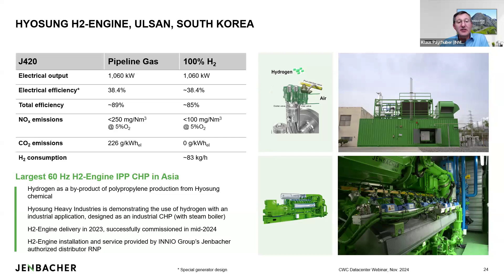What you can also see on this chart is the NOx emissions -- they significantly go down between natural gas operation and hydrogen operation. When running on 100% hydrogen, this engine produces less than 50% of the NOx emissions. The hydrogen comes from a polypropylene production as a byproduct, and the engine is installed and designed as a CHP unit. It was delivered last year, installed this year, and for a couple of months it has been in operation on 100% hydrogen.